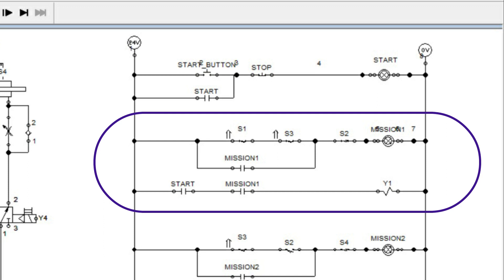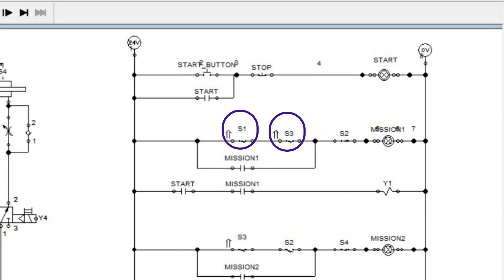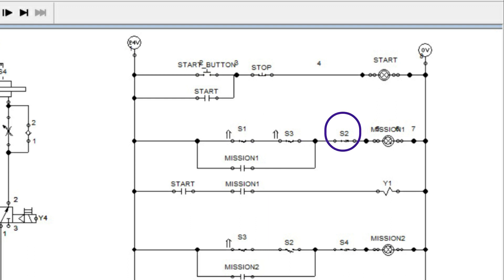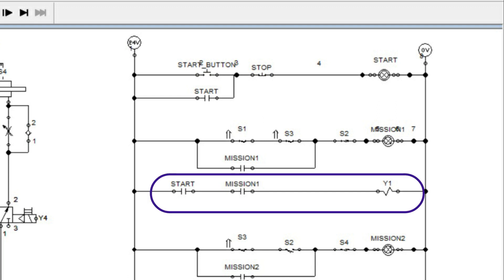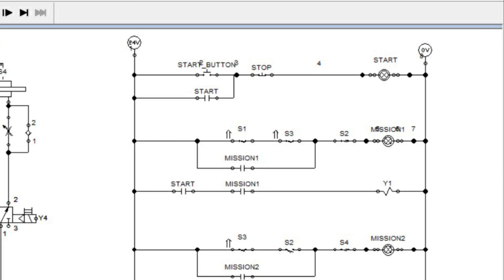This network represents Mission 1: extension of cylinder A. The start condition is S1 and S3, and the mission-done condition is S2. Initially there is a power flow to the Mission 1 memory, and it produces a seal-in path keeping Mission 1 memory high until cylinder A reaches the fully extended position. When start memory and Mission 1 memory are both high, there is a power flow to the Y1 solenoid, and cylinder A is extended.